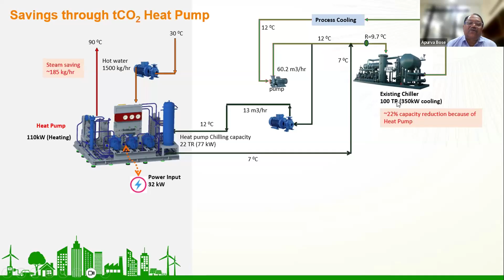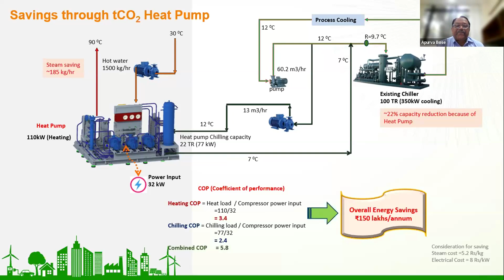If you do the calculation of COP, it comes out to be 5.8, and the energy savings come out to be 150 lakh rupees per annum, assuming steam cost is 5.2 rupees per kg and electricity cost is 8 rupees per kilowatt. I will show you a detailed calculation for one more similar exercise going forward, but this is what I wanted to show here: the advantage of using the natural heat pump is immense.